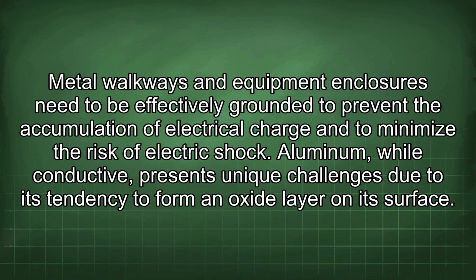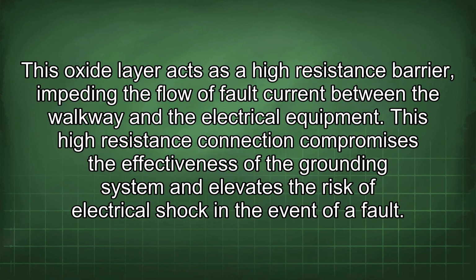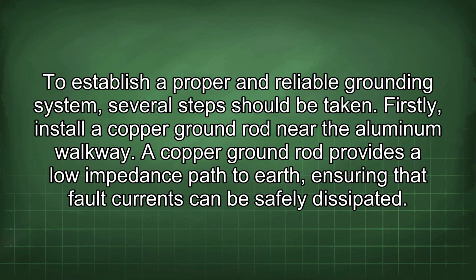Aluminum, while conductive, presents unique challenges due to its tendency to form an oxide layer on its surface. This oxide layer acts as a high-resistance barrier, impeding the flow of fault current between the walkway and the electrical equipment. This high-resistance connection compromises the effectiveness of the grounding system and elevates the risk of electrical shock in the event of a fault. To establish a proper and reliable grounding system, several steps should be taken.